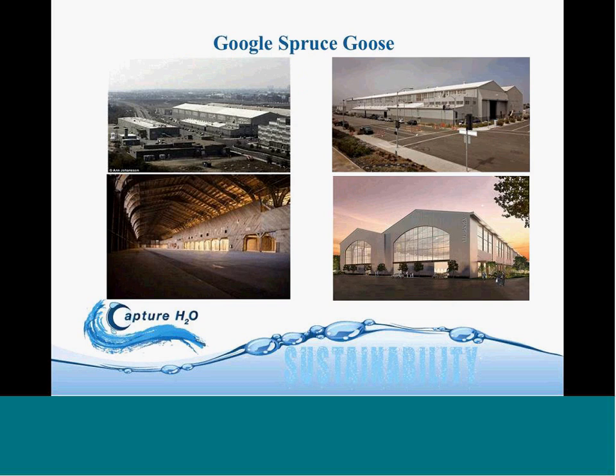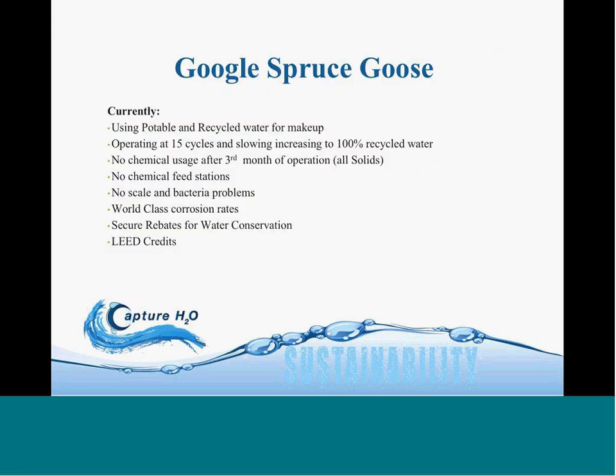The pictures here on the left show the 1940s building, the Spruce Goose hangar, and the ones on the right show what it looks like today after they repurposed the building and built out the inside. Currently they're using both potable and recycled water for cooling tower makeup. They're operating at 15 cycles, and we started to meet their minimum of 20% recycled water, but we're slowly increasing it, and we're going to use 100% recycled water in that cooling system.